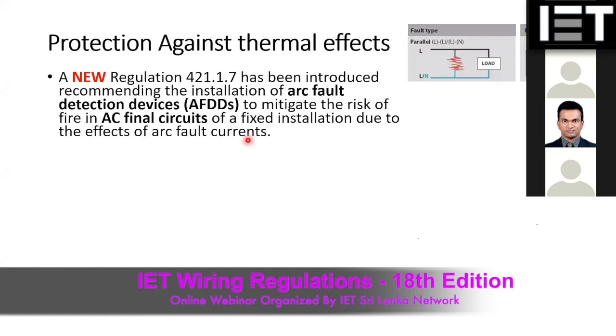That is what we call parallel arc faults. And also there can be live to earth, that is an earth fault. For the earth fault, traditionally we provide an RCD, so that will take care of the earth fault. But the arc fault detection devices can also detect this type: if there is an arc, that will also be detected by these devices.